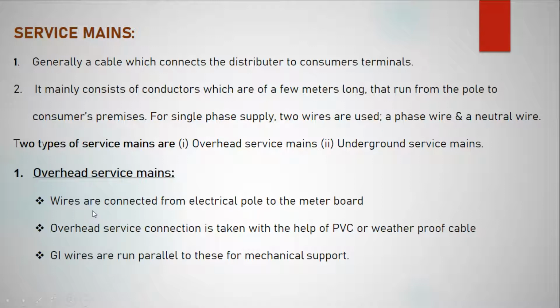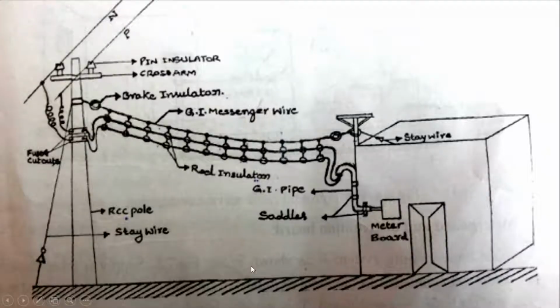In overhead service mains, the wires are connected from the electrical pole to the meter board. These overhead service connections are taken with the help of PVC or weatherproof cables. GI wires are run parallel to these for mechanical support. Let's see how it looks.